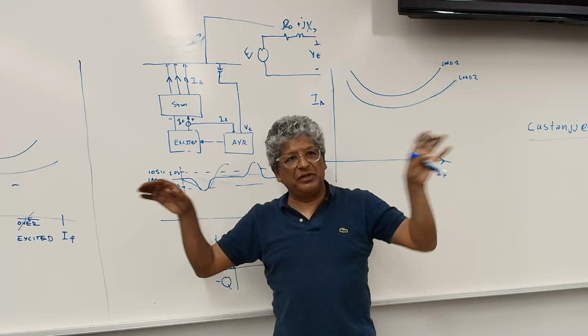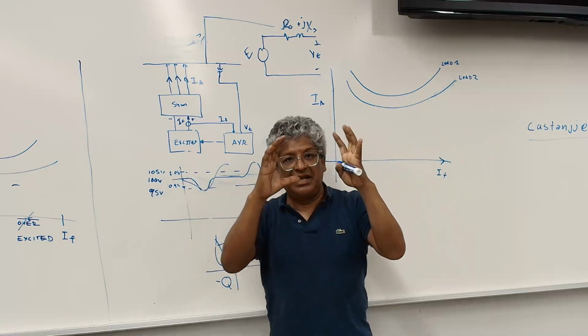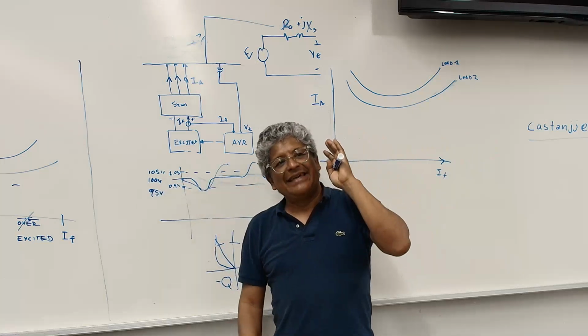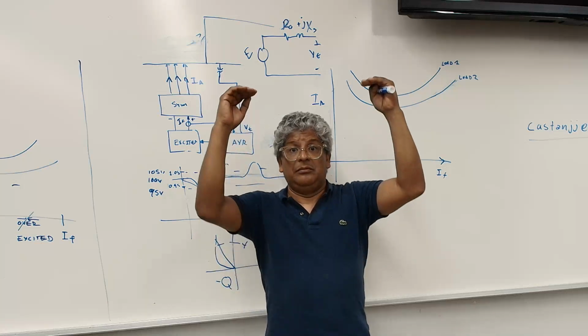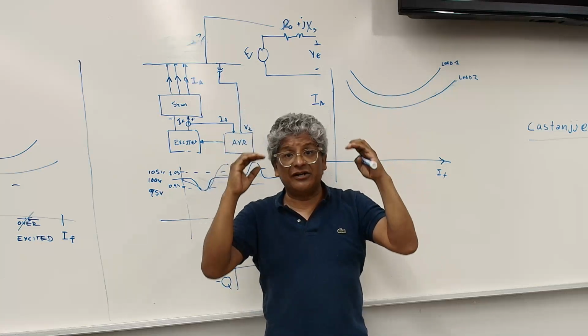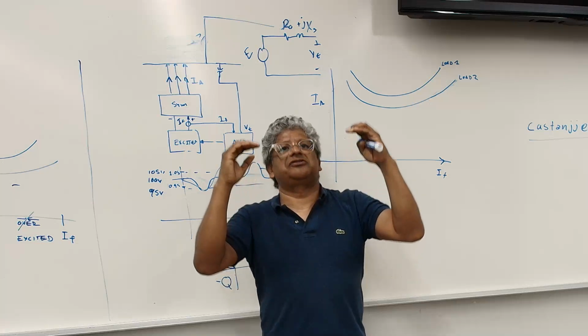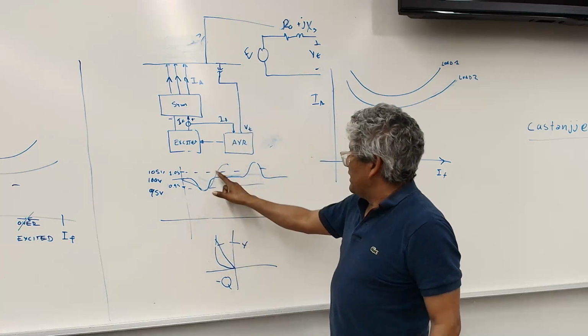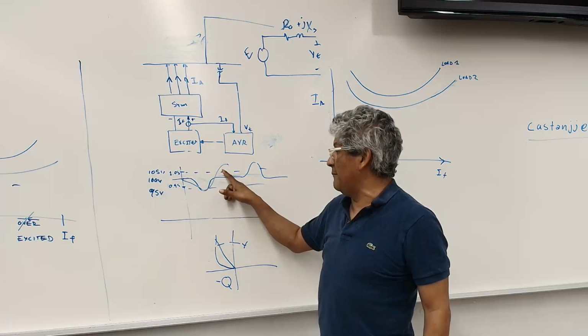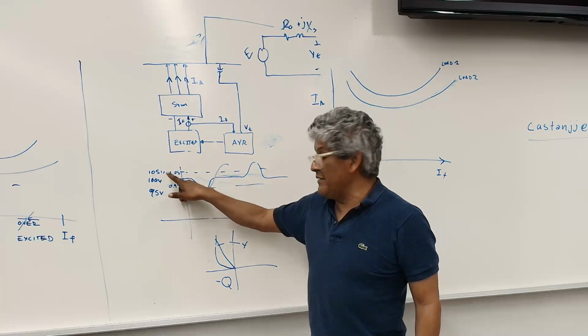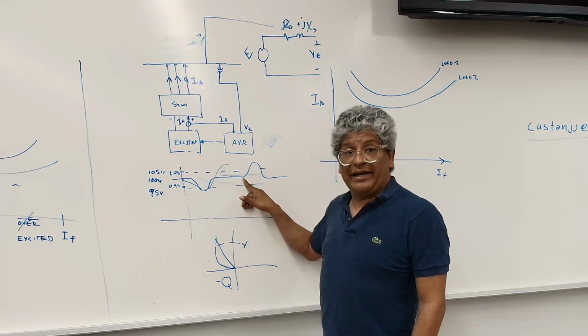Say we're in this building, and all of the loads in this building are connected to the same source, and then you drop 90% of this building. The voltage goes up, right? Because the demand in VARs goes down, and the voltage starts creeping up. So if you go to 105 volts, that's your limit. You've got to bring it back to one again.